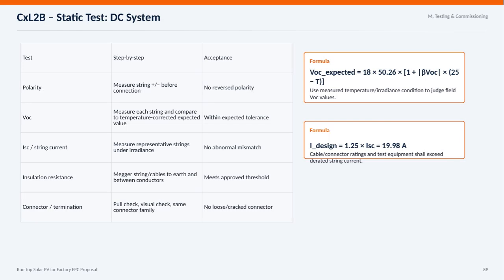Here we have the static test procedures for the DC system of the rooftop solar PV installation. First, we check the polarity by measuring the string's positive and negative terminals before connection, ensuring there's no reversed polarity, which is critical for safety and proper operation. Next is the open circuit voltage, or VOC, where we measure each string's voltage and compare it to the temperature-corrected expected value using this formula. This lets us confirm the VOC is within expected tolerance under current field conditions.